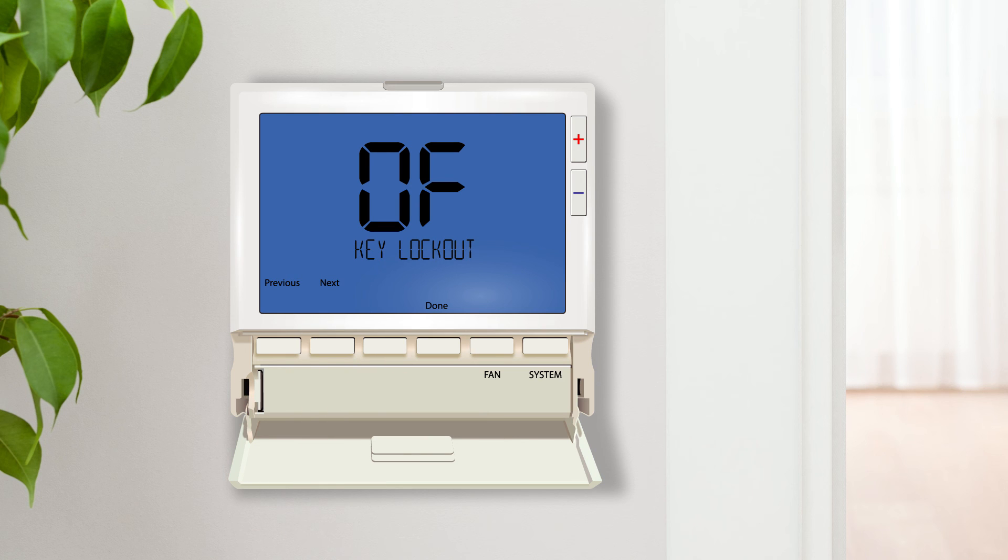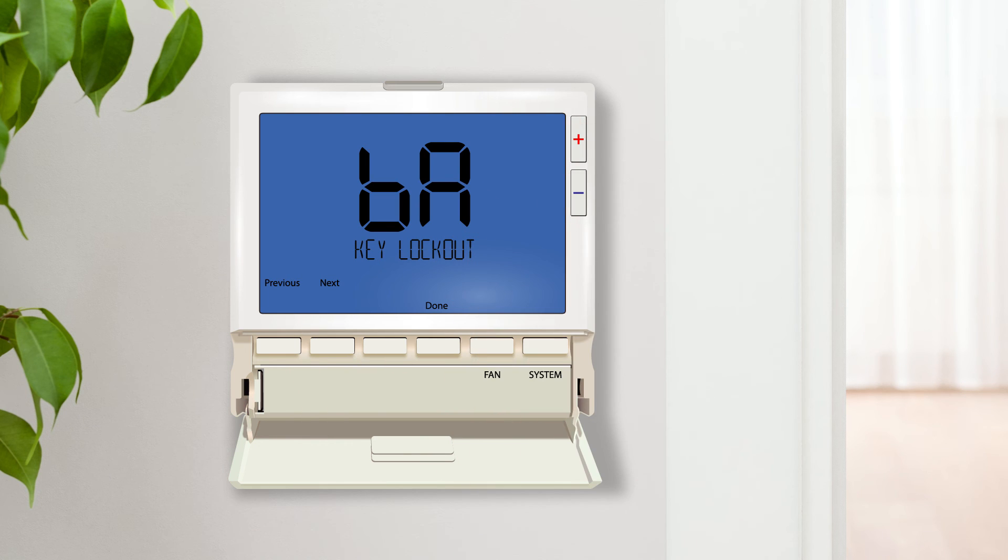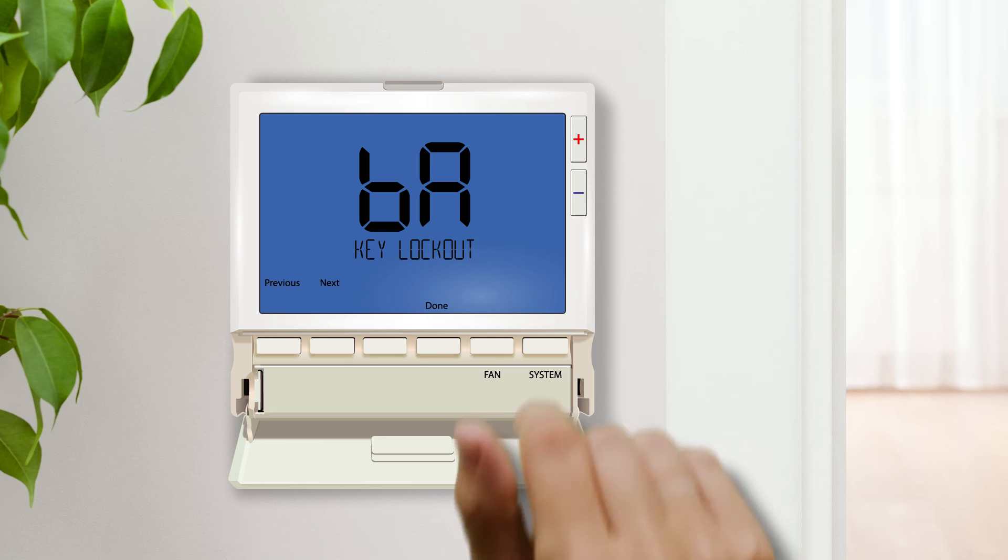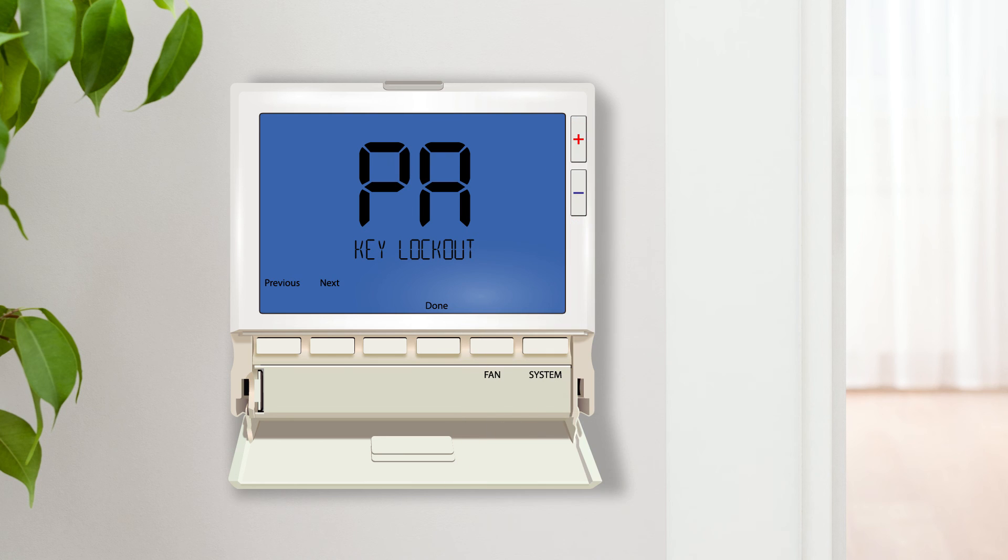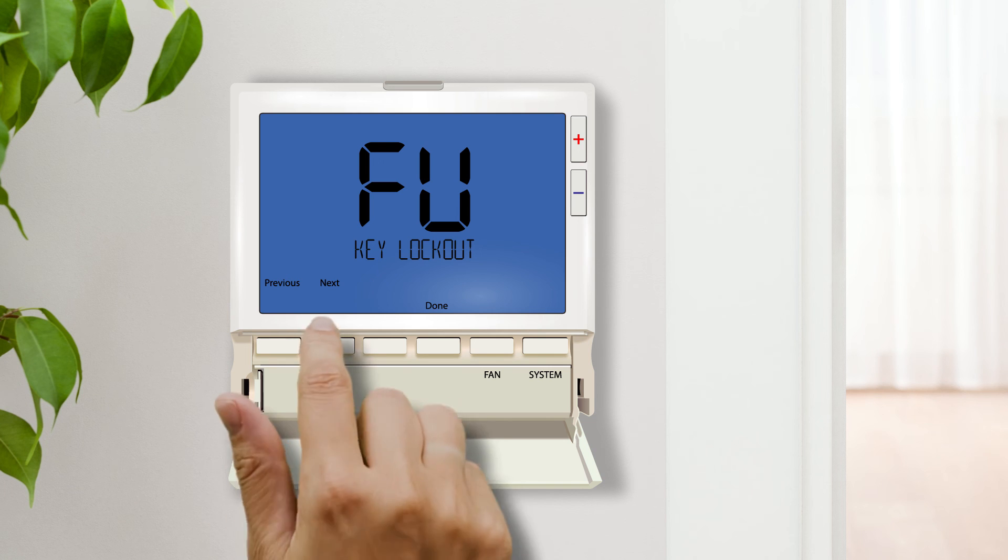Keypad lockout allows you to configure the thermostat so some or all of the keys do not function. Partial lockout allows the user to change the temperature but disables the menu or hold buttons. Full lockout disables all buttons. Once turned on this feature is engaged and disengaged by holding down the plus and minus buttons for 3 seconds. This feature is very popular in commercial buildings and rental properties.